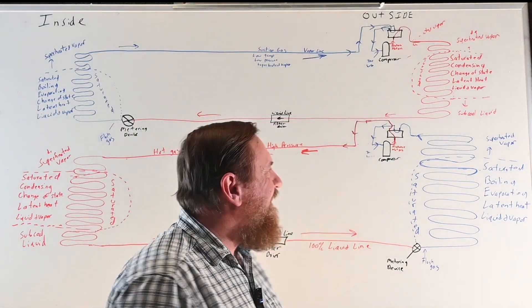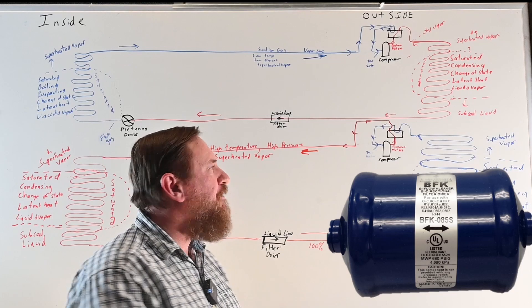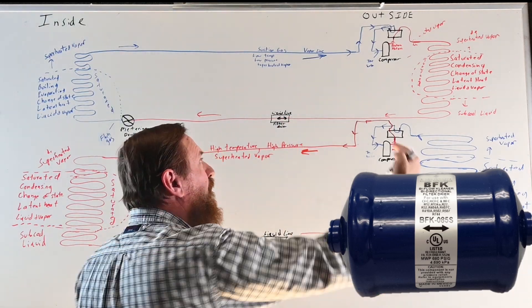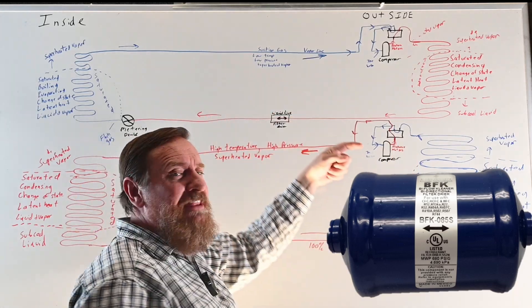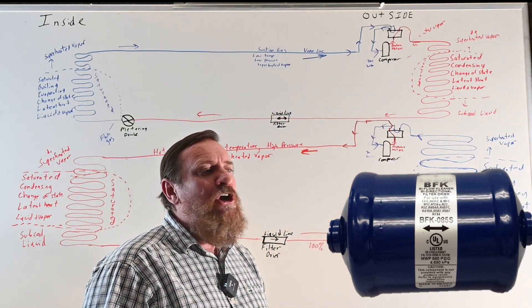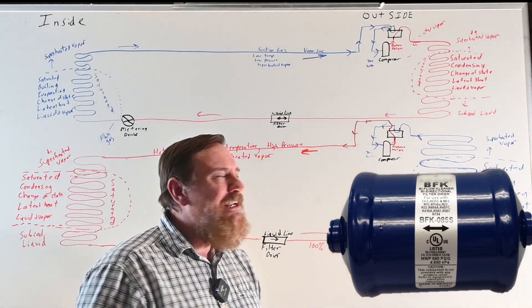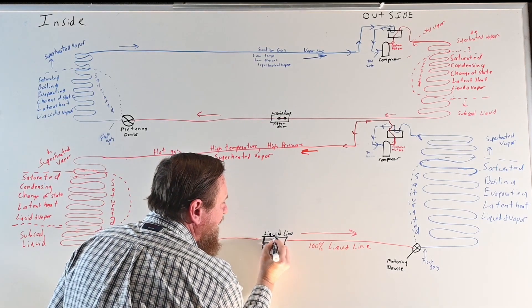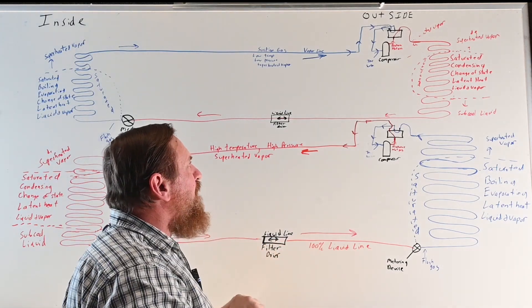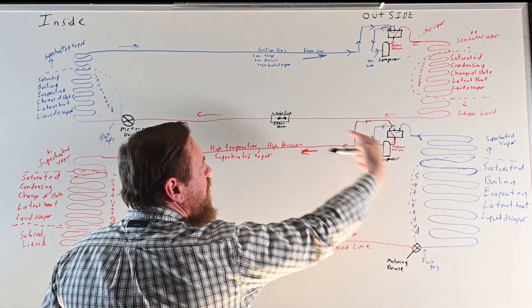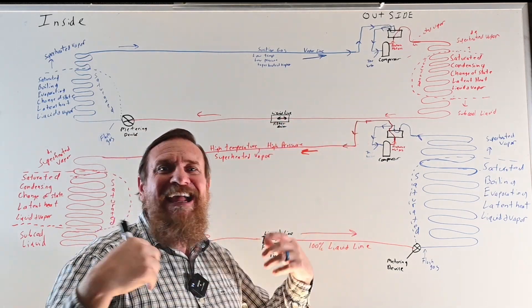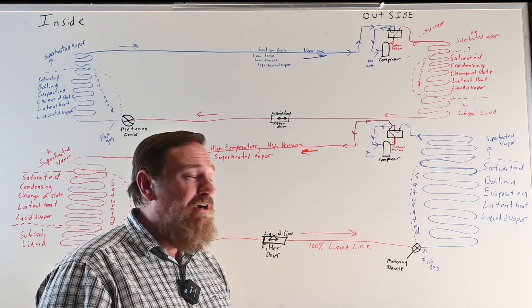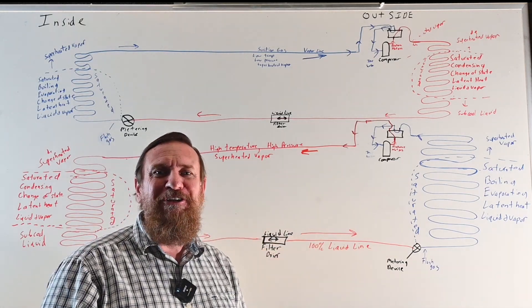So what we use is a bi-flow filter dryer. This filter dryer will filter refrigerant in either direction — whether the refrigerant is flowing this way or that way, it's still going to filter it. We'll have that same bi-flow filter dryer on both sides, so no matter which way it's flowing — summertime one direction, wintertime the other — it's still filtering the refrigerant.